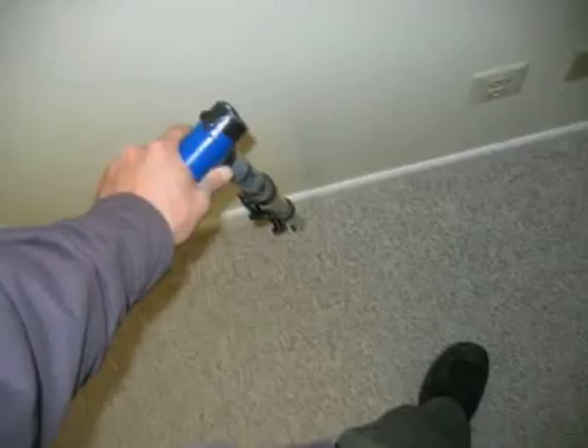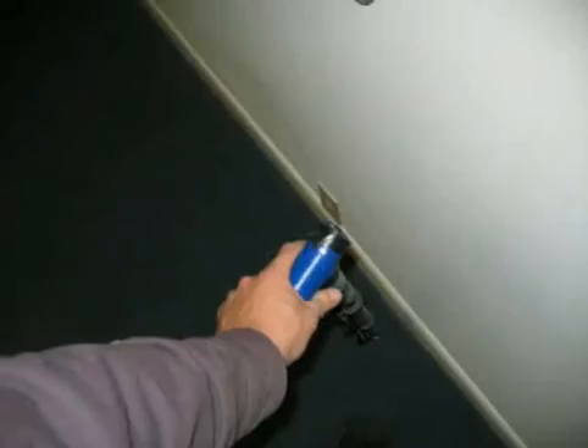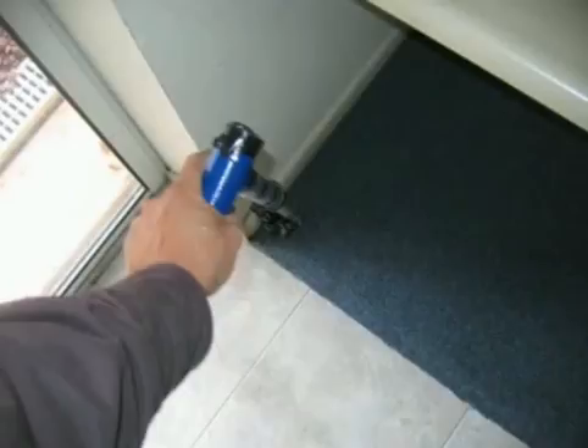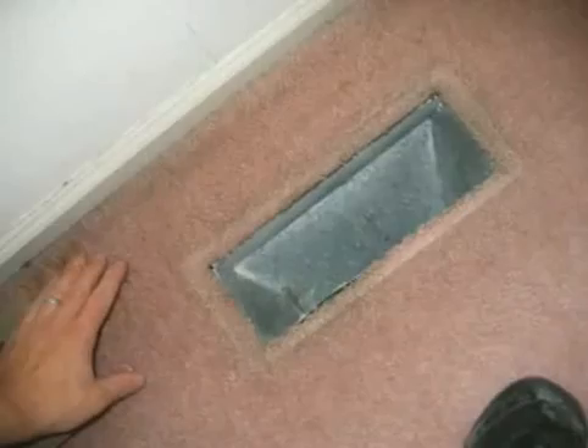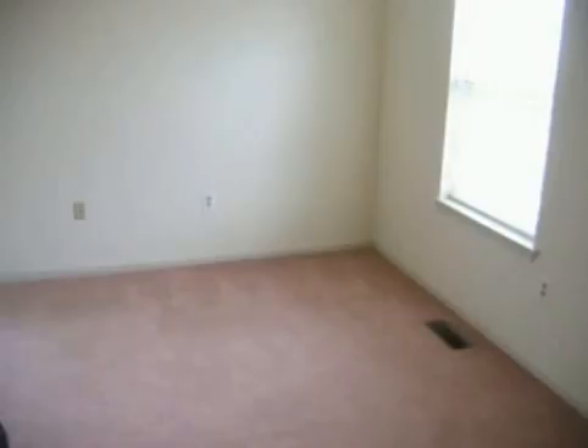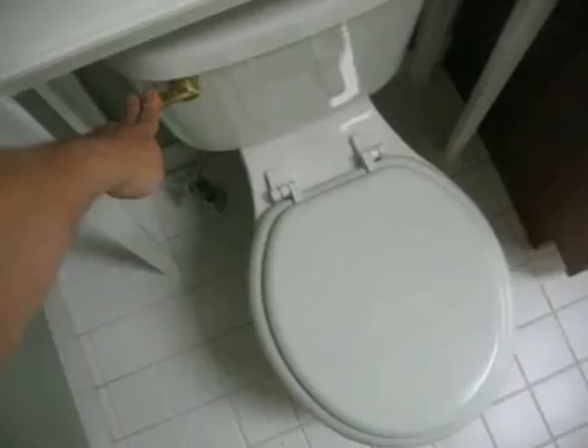Look at the basement stairs underneath the crawl space. Have a little moisture meter that probes the carpeting. Looking for a qualitative result. Check the air supply registers. Since the air filter of the HVAC system was dirty and delayed maintenance. Delayed maintenance on an HVAC system is a condition that's conducive to mold growth.